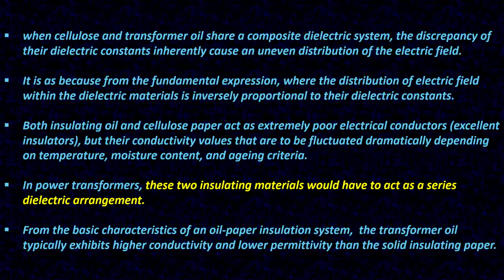Another important point. When cellulose and transformer oil share a composite dielectric system, the discrepancy of their dielectric constants inherently causes an uneven distribution of the electric field. It is because, from the fundamental expression, the distribution of electric field within the dielectric materials is inversely proportional to their dielectric constants.